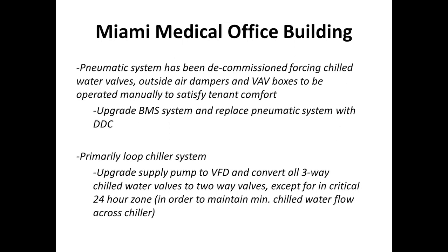Chill water was piped directly to the building and back to this chiller. Because of this, we couldn't recommend... The way that this chiller was set up was that each unit had a three-way valve, and one of the main issues was that since these three-way chill water valves were no longer being pneumatically actuated, whatever position they happened to be stuck in determined how much chill water was allowed to flow through the chill water coil.